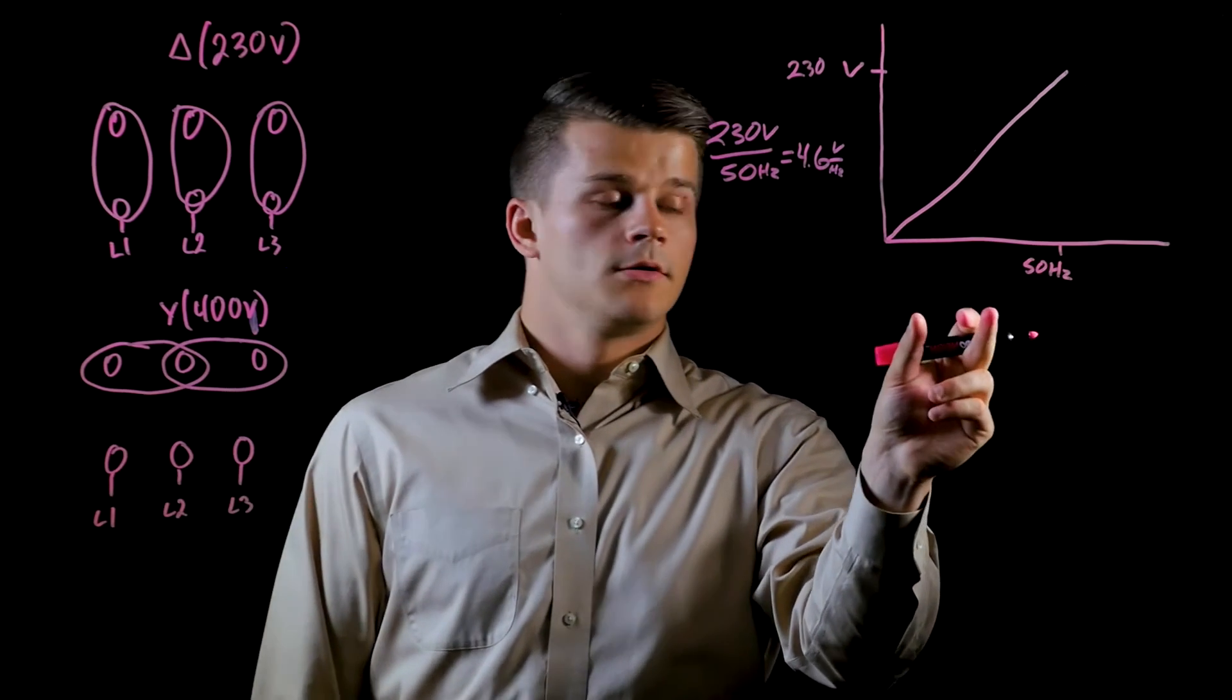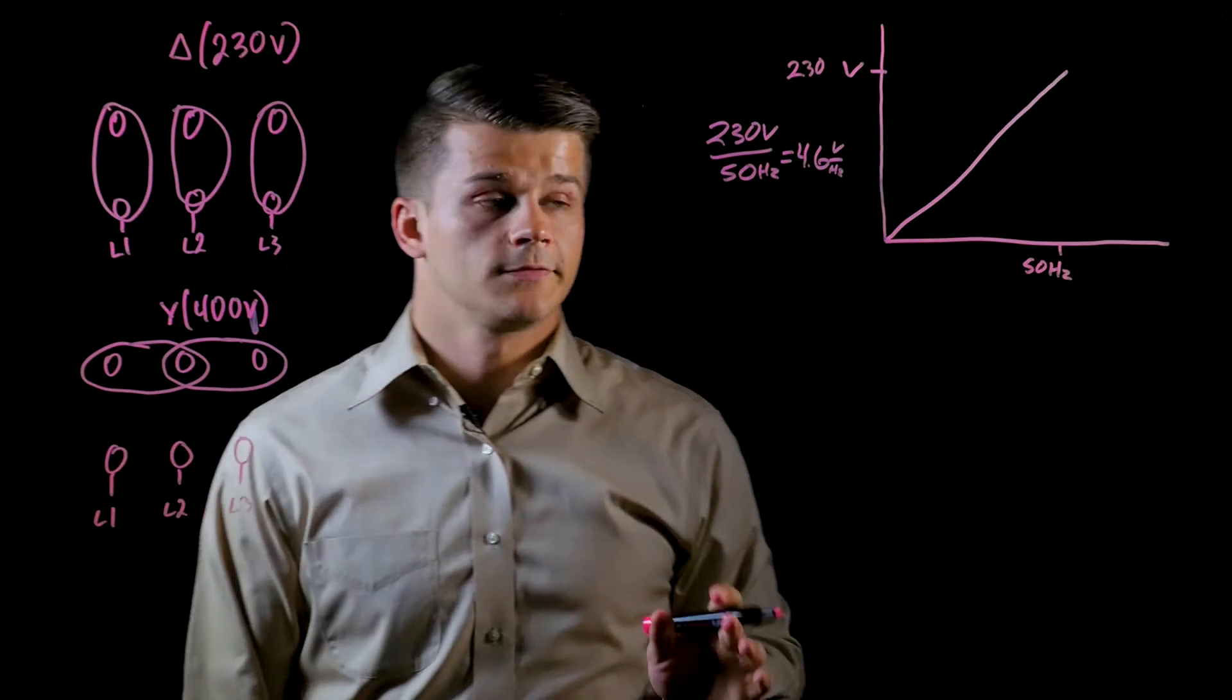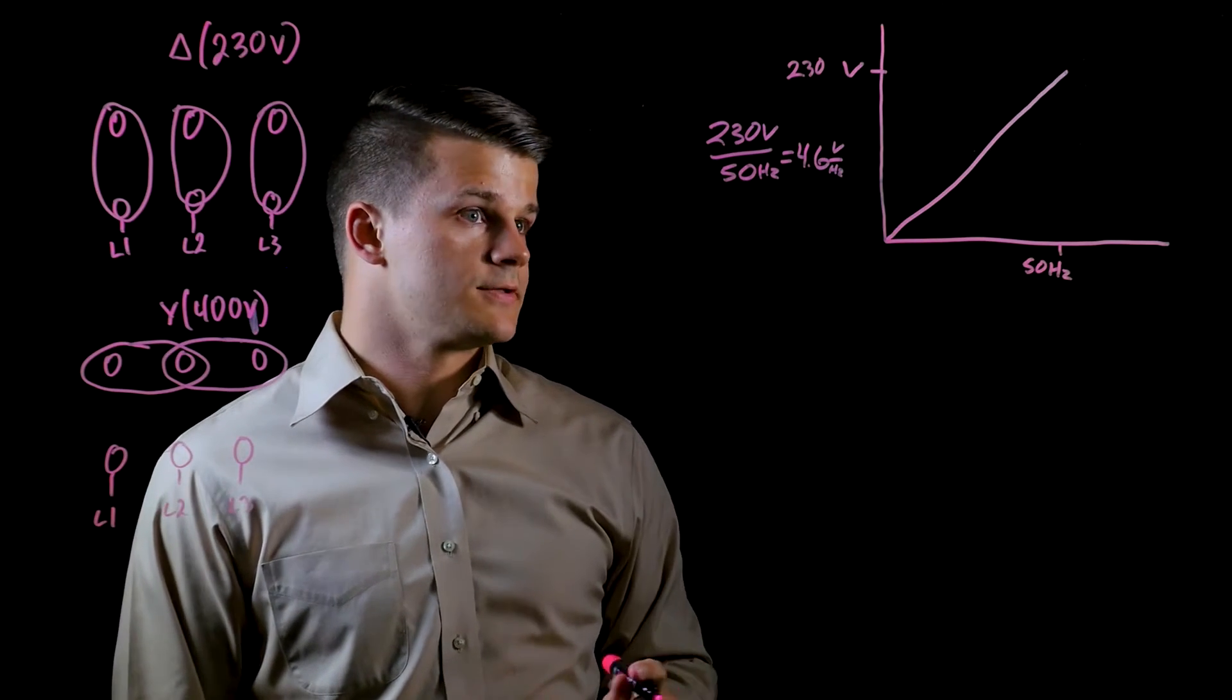For every one Hertz we increase the frequency, we have to increase the voltage by 4.6 volts. As long as that stays constant, we'll have constant torque.